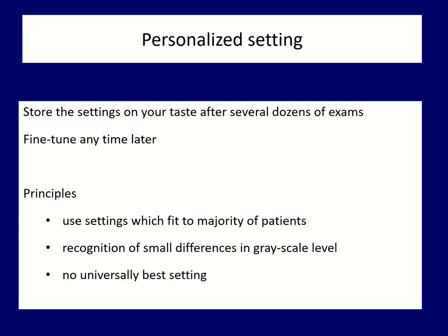It is worth making these settings at the very first occasion when we use equipment and thereafter storing them as a unique preset. All equipment allows us to store individual settings which can be saved with an appropriate name. If more colleagues use the same ultrasound, it is highly advised to use the name of the different investigators.